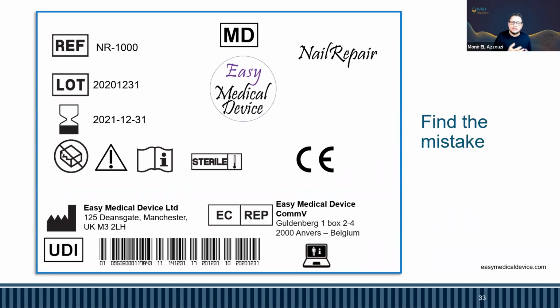And as you've seen, if you have a notified body number, then you are class 1S, class 1M, class 1R, class 2A, class 2B, or class 3. But if there is no number like this one, then it's a class 1, because class 1 is self-certified. So normally there is no notified body number.